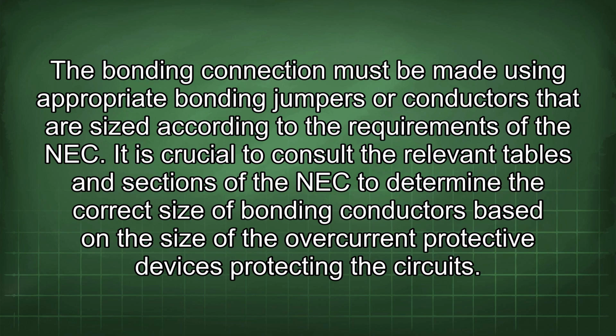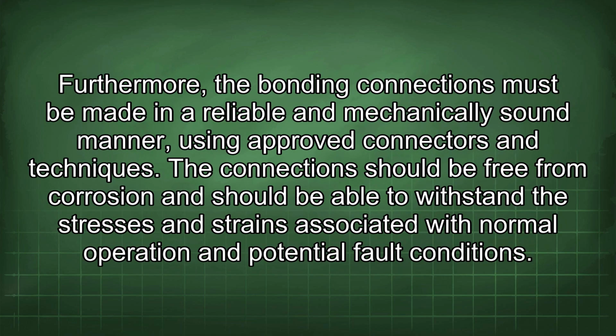It is crucial to consult the relevant tables and sections of the NEC to determine the correct size of bonding conductors based on the size of the overcurrent protective devices protecting the circuits. Furthermore, the bonding connections must be made in a reliable and mechanically sound manner, using approved connectors and techniques. The connections should be free from corrosion and should be able to withstand the stresses and strains associated with normal operation and potential fault conditions.